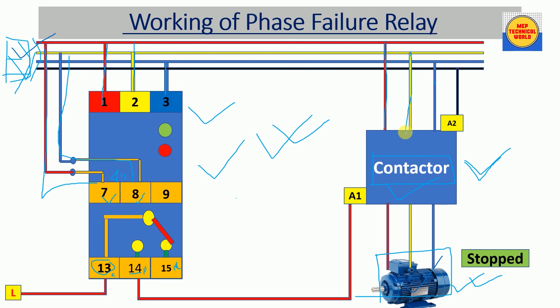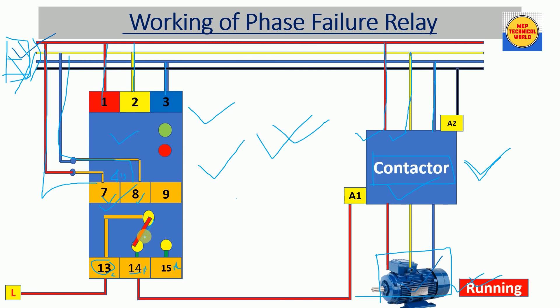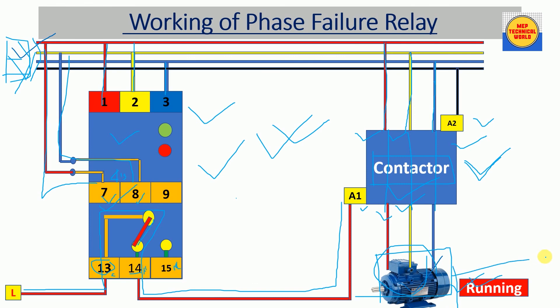When we connect R, Y, B phases and apply 415 V across the bus bar, the relay receives three-phase power and the auxiliary contact also gets its 415 V supply. The three phases are also available at the input terminals of the contactor. Since everything is okay, the relay coil energizes, NO contact becomes NC, and power flows through to the contactor coil. The contactor energizes, completes the circuit, and the motor receives power and runs.